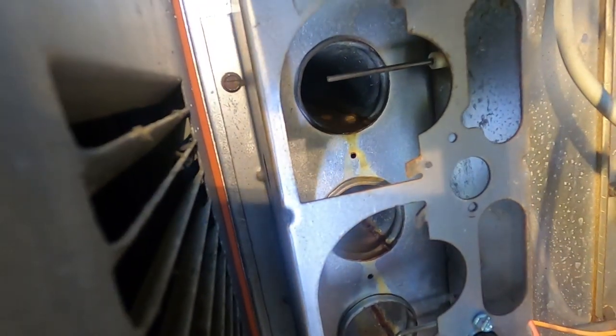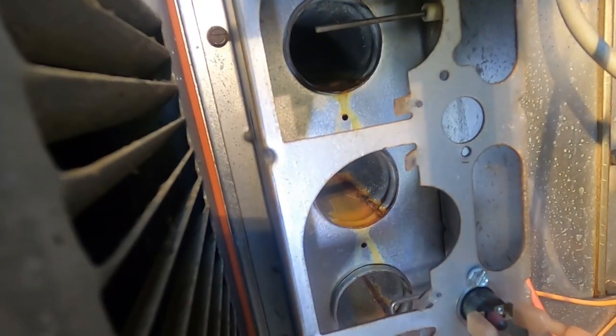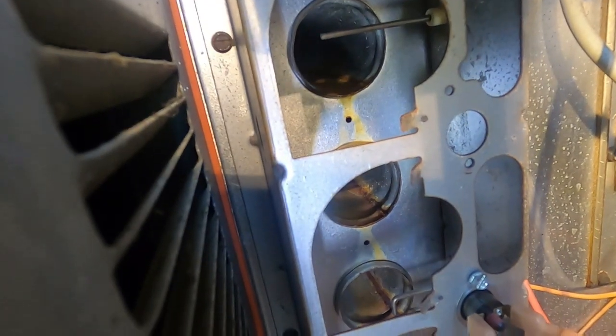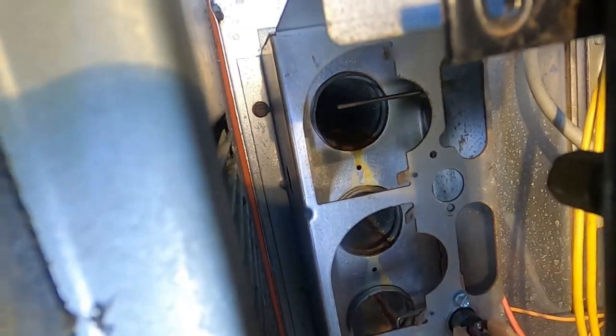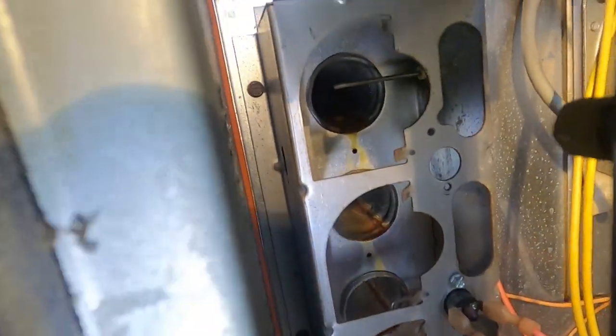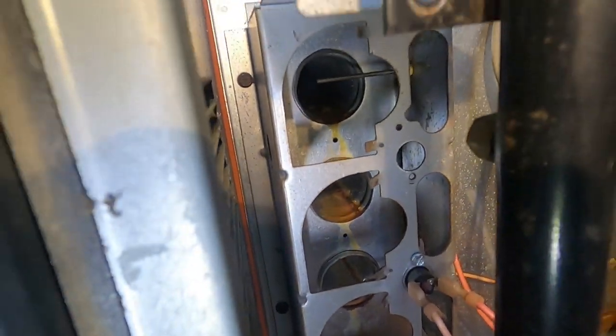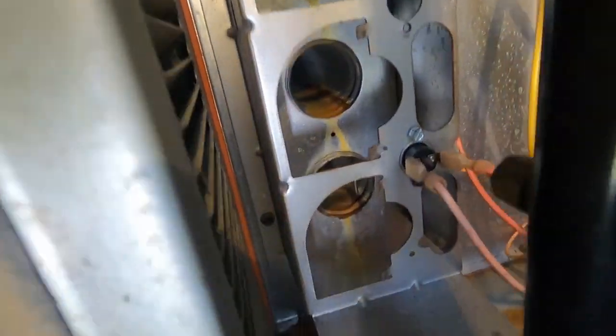But when the blower comes on, it blows against the back of those screw holes, and it also blows heat back out through there. And every time that we have put one of these heat exchangers in and forgotten to take that off and put it on, which has happened 2 or 3 times, we were right back out there not too long after with rollout problems.